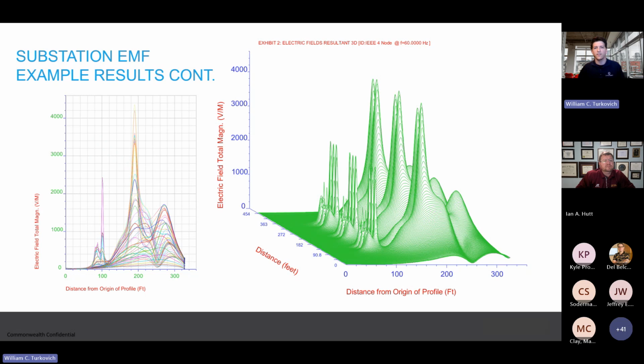Here's another way of displaying that graph, two-dimensional on the left screen, which you can compare to the right to put the pieces together. You can still see, comparing the left graph to the side profile of your substation, that this is the transformer, that's the connection tie, that's the breaker, here's the collector station, and here are the peaks in volts per meter. We're seeing a super high peak around 4,400 volts, 4.4 kV per meter, at those transformer high sides.